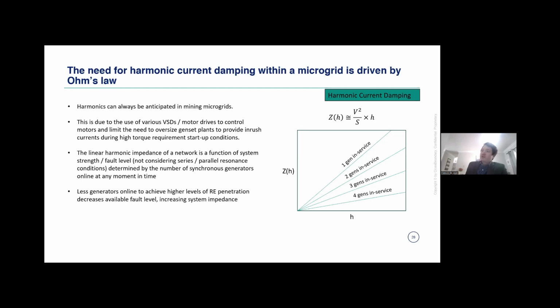And the challenge with integrating renewable generation within microgrids is that essentially what we're trying to achieve is to reduce diesel generation or HFO generation. And by doing that, we're actually removing gensets from the system, which reduces the fault level or the system strength of the system. And the less fault level we have, the higher becomes the linear harmonic impedance of the network. So again, sorry if it's getting overly complex, but what I'm trying to say is the less generators you have, the higher your impedance of the network. And if we apply Ohm's law, if we have a higher impedance, it doesn't take a lot of harmonic current for us to sit with very high levels of voltage distortion in the system, compared to a system that's only supplied by diesel generation.